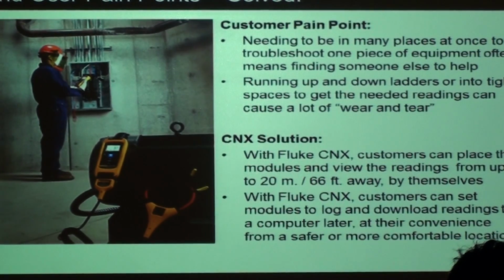A perfect example is testing starting currents and motor inrush. Before, it was possible with a clamp meter to measure the inrush, but with inrush currents you also want to measure the voltage drop at the same time, which sometimes needs two people. With the CNX solution, I connect the voltage test leads on the panel side and the flexible current module on the motor. I set it to inrush mode, and as soon as I flip the switch, I see both the inrush and the voltage on my master meter at the same time, allowing me to isolate the problem. With a distance of 20 meters, anything is possible.